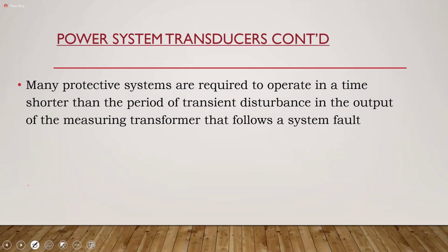However, within a power system, when I say a breaker takes 300 milliseconds to operate, well, that's even too long. When I say a breaker takes 150 milliseconds, just the breaker, to operate, within the sphere of protection that seems like a lifetime, because we are dealing with breakers that are operating in 60 milliseconds. That's the type of time we're dealing with. We need to be clearing a fault within 200 to 300 milliseconds. And when I say clear, I'm including both the operating time of the breaker plus the time that the relay senses and all of that.